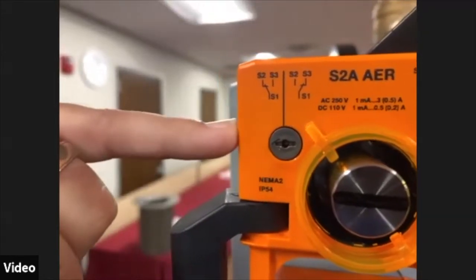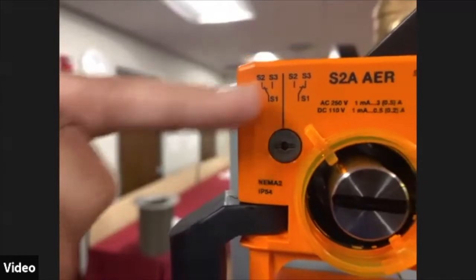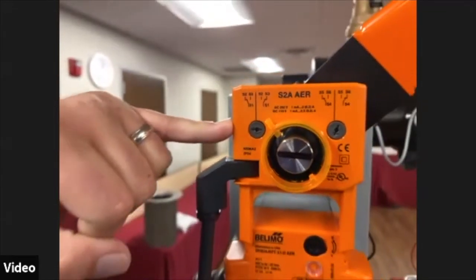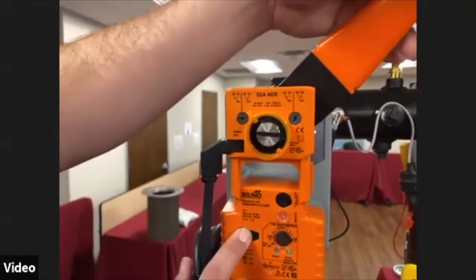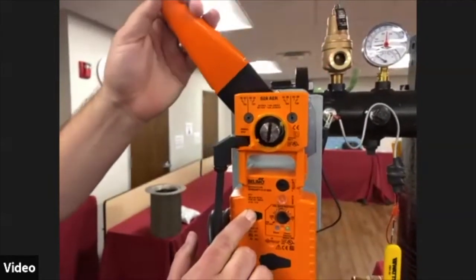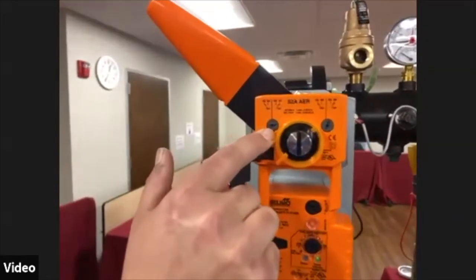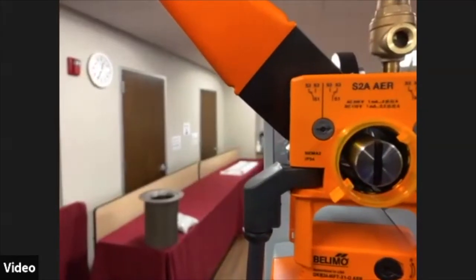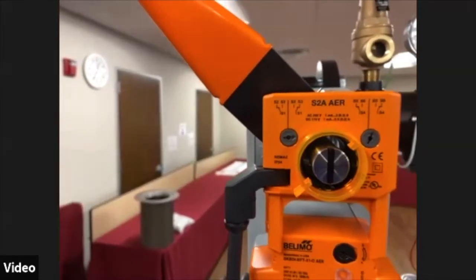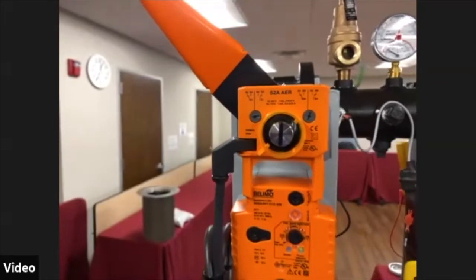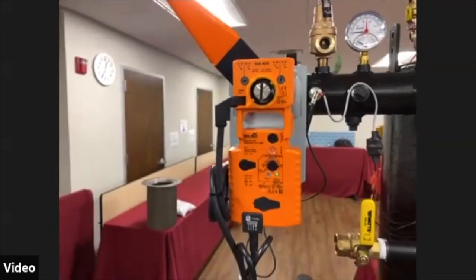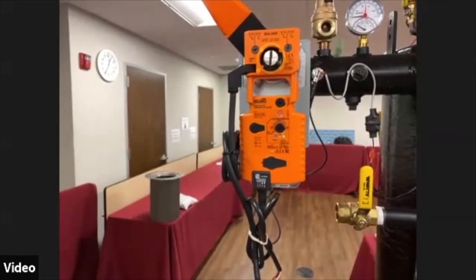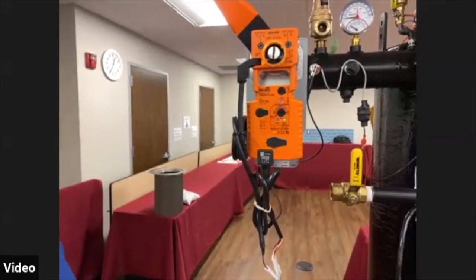If the valve is in the open position, which it is right now, we can tell by the shaft, then the end switch should be adjusted to about 9 o'clock. If this was a clock, it should be pointing at 9. If the valve is closed when you set it, you see it points towards 3 o'clock. And you hear the valve is moving because it should be open right now because the boiler's not firing. So I'll get into a little bit of the maintenance that we go through.